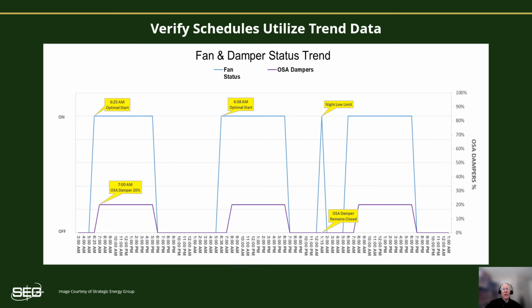Now in this graph, the blue line represents the fan status, and the purple line represents the outside air damper position. The fan system appears to have optimal start and morning warm-up functioning. Notice how the optimal start time varies here, sometime after 5 o'clock in the morning. Notice also that the dampers remain closed during the early start time. This is what we want them to do. There's no sense in having to heat up cold outside air when nobody has arrived in the building yet.